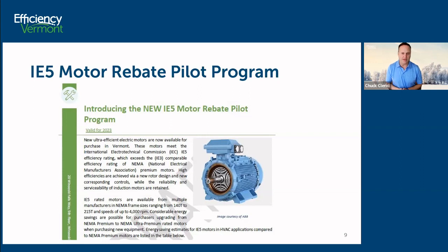And then in non-manufacturing, a lot of the connected load, aside from lighting, is motor load in HVAC and refrigeration and other equipment. So a lot of what we have on the grid is motor load, and yet we haven't been able to provide motor rebates. And the reason for that is that the federal government made NEMA premium efficient the federal standard. It might have been 2007 or one of the years shortly before that. So in the United States, all you can sell are NEMA premium efficient motors. Those equate to an IE3 motor rating.